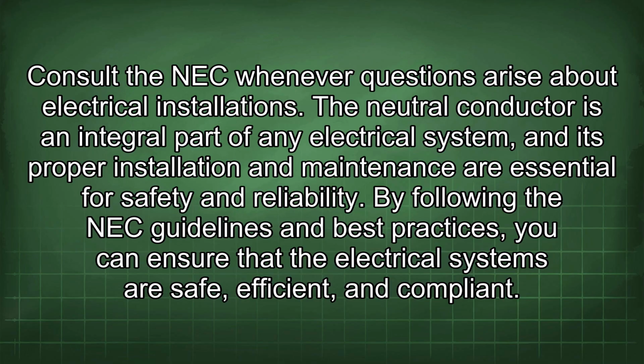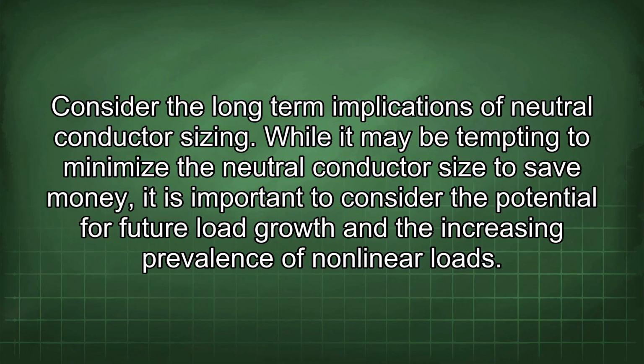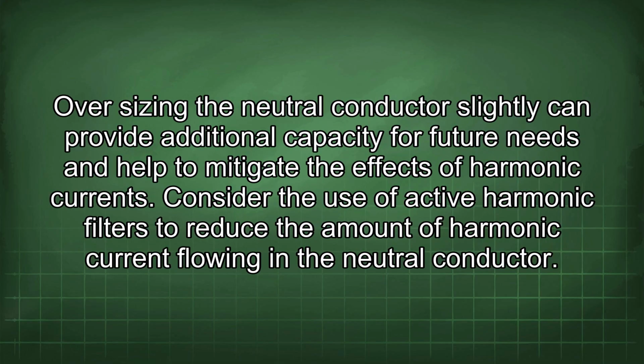The neutral conductor is an integral part of any electrical system, and its proper installation and maintenance are essential for safety and reliability. By following the NEC guidelines and best practices, you can ensure that the electrical systems are safe, efficient, and compliant. Consider the long-term implications of neutral conductor sizing. While it may be tempting to minimize the neutral conductor size to save money, it is important to consider the potential for future load growth and the increasing prevalence of nonlinear loads. Oversizing the neutral conductor slightly can provide additional capacity for future needs and help to mitigate the effects of harmonic currents.